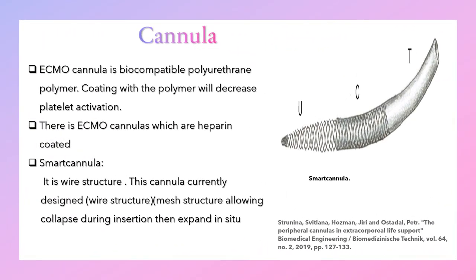ECMO cannulas are made of biocompatible polyurethane polymer. Coating with this polymer decreases blood clot activation. They are also heparin-coated. A newer type is called the smart cannula — it has a wired structure where part of the cannula is uncovered, forming a mesh of wire that allows collapse during insertion. After insertion, it expands in situ to allow better fixation.